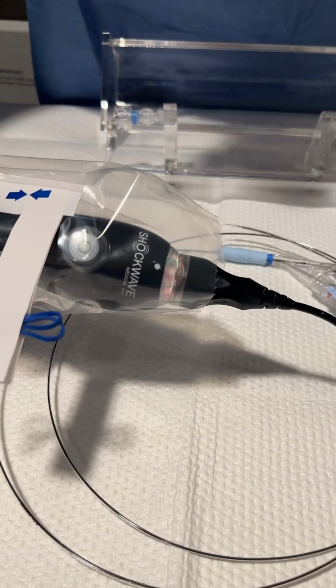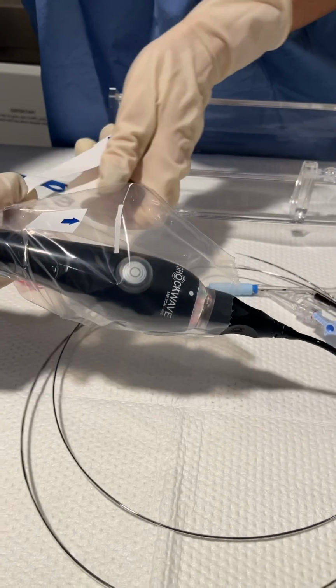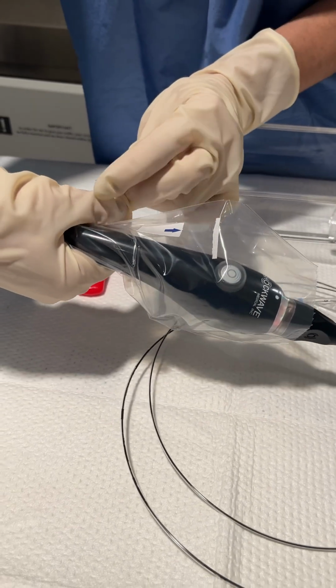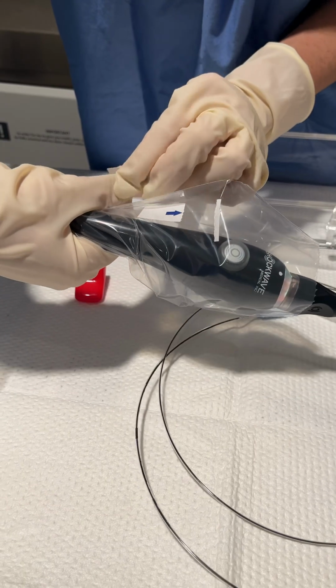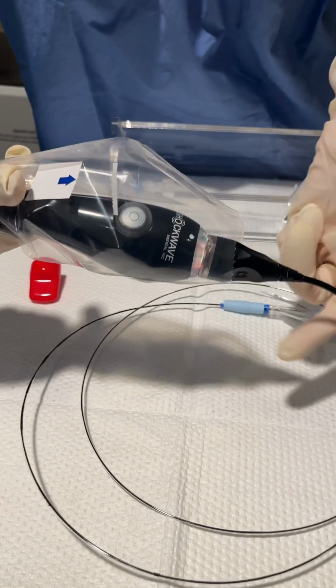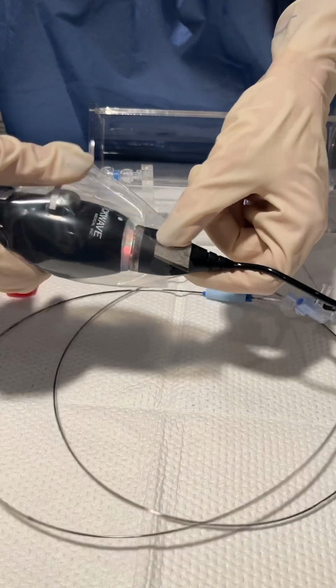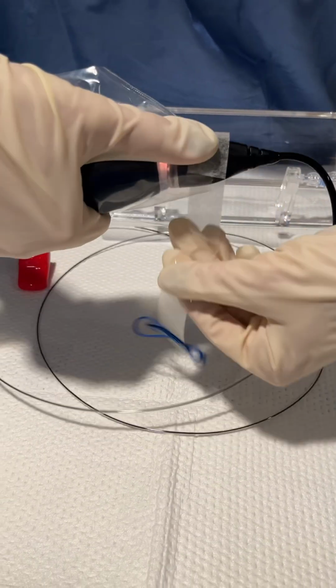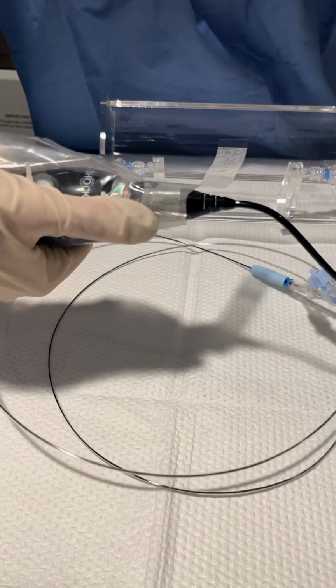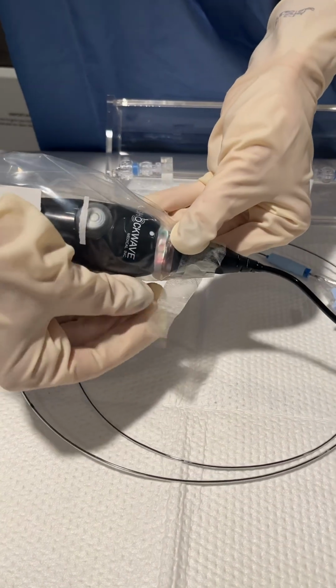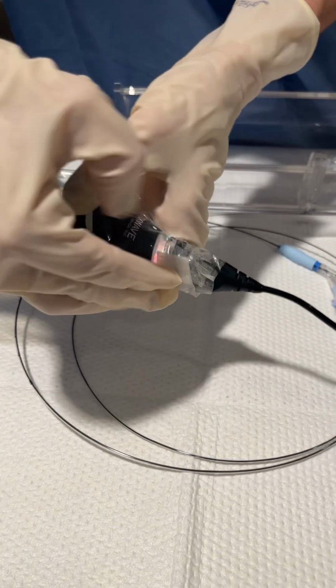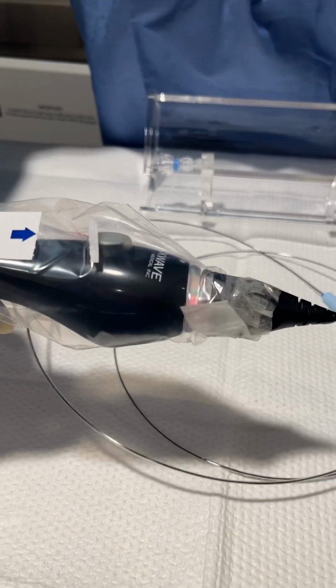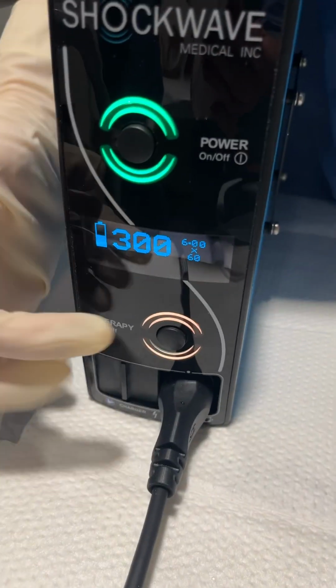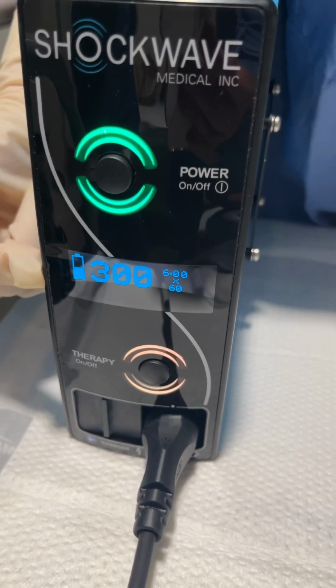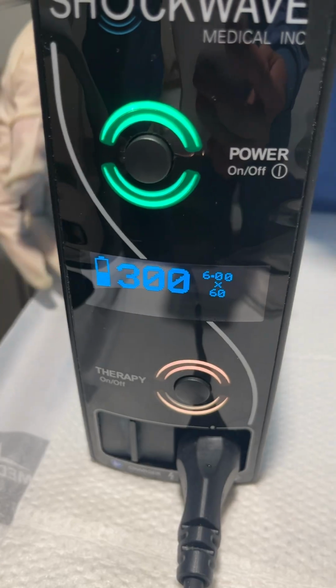And then we secure the edge of the bag with either Tegaderm or tape. Tape is provided. Okay, so tape is going to secure the edge of the bag on the catheter hub. Rubber bands are not necessary. Just keep wrapping, and then we do recommend to fold the final edge to give you flexibility to untape it if you need to. Okay, once the device is connected, it will then show the amount of pulses and the size of the balloon. This M5 Plus comes with 300 pulses, and this is a 6x60 balloon.